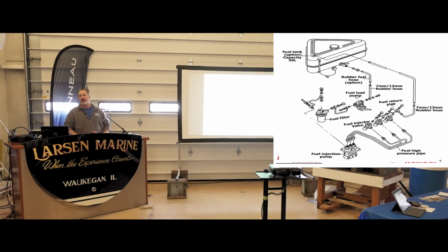For us, I don't have a set recommendation for when you should do it, but you keep an eye on it through your filters. When you change your filters, our technicians are trained, and if they see something abnormal in the filter, they'll flag it. That may just be the filter doing its job, or you may have something in your tank. That's usually the indication we use to recommend action, or if you're doing it yourself, if you see a lot of stuff in that primary fuel filter, you may want to take a sample off the bottom of your tank, and if that sample shows stuff, then you'd clean it.